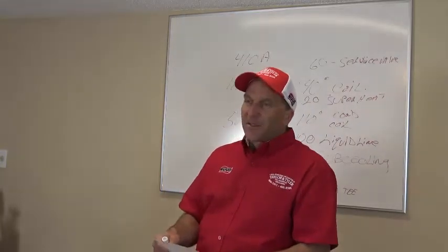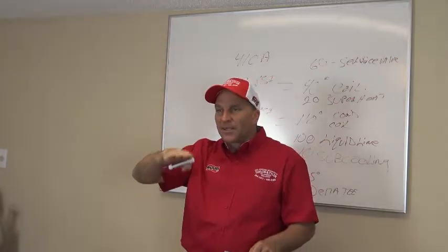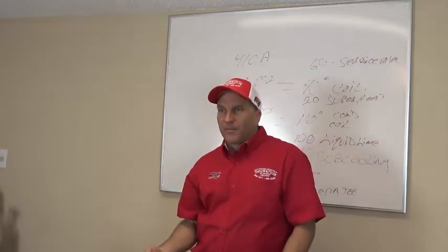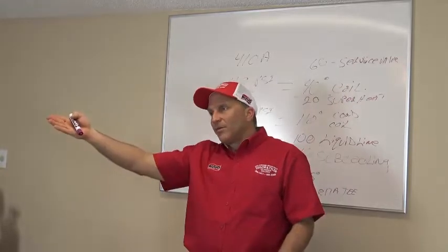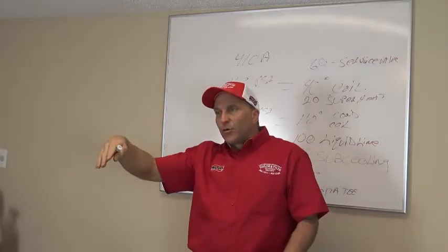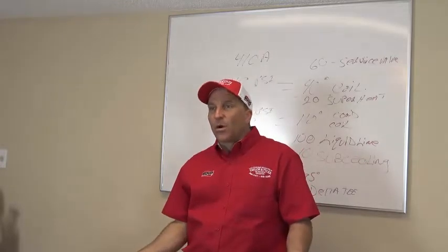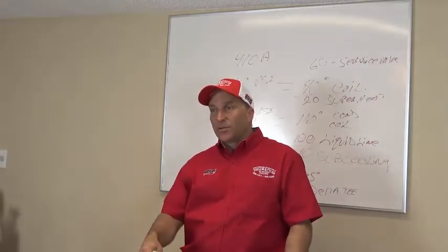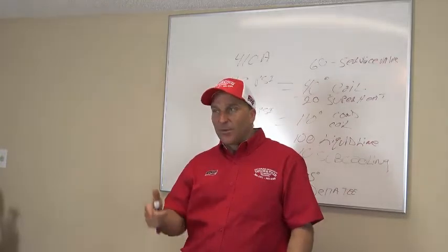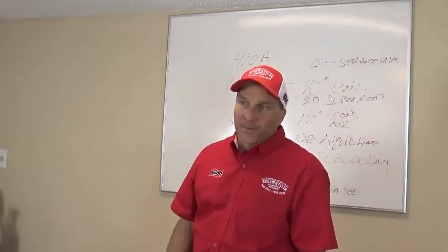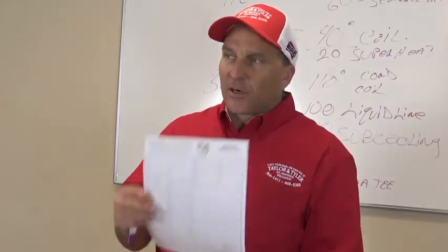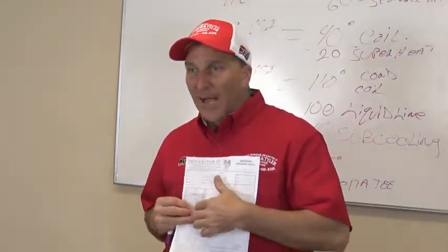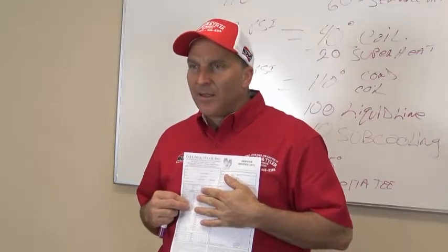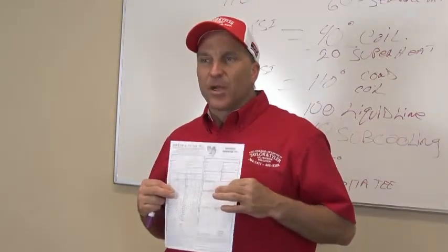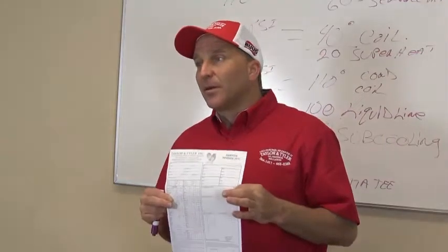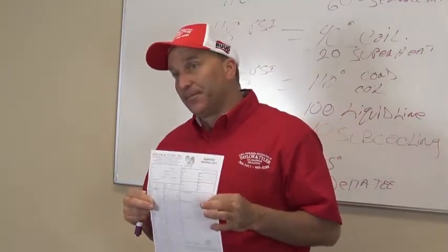Service valve caps. How many times did you go on the service valve, the top of the service valve? There's no cap on it. Okay, well we got a whole bunch of them in the room over there. In your toolbox, you should have a few of them, just in case you get to one of those systems. Because I'm telling you, if you go service the system and you turn around and leave and it's leaking two weeks later, it's your fault. Did you note on here that the service valve caps are bad, or missing, absent? Did you make a recommendation to replace them? If the answer is no, you didn't make that recommendation to replace them, it's your fault it's leaking then. Okay?